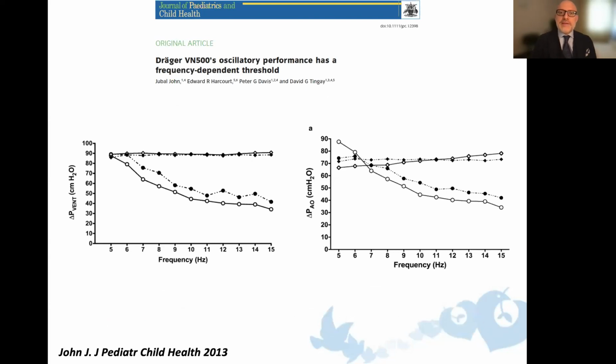This other paper is coming from David Tingay from Melbourne, my good friend, has been the first one demonstrating that the new, relatively new Dräger machine, the VN500, is actually unable to provide a constant amplitude at the ventilator here on the left or on the endotracheal tube while increasing the frequency. You see the gold standard is again the same ventilator, you know, with a flat line, but the performance of the VN500 is very much decreasing over increasing frequency. And this is something that has been described for the very first time in 1997 with the old Babylog, which actually shares the same technology with VN500.